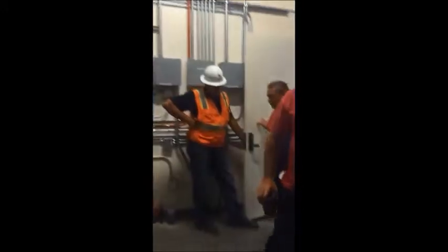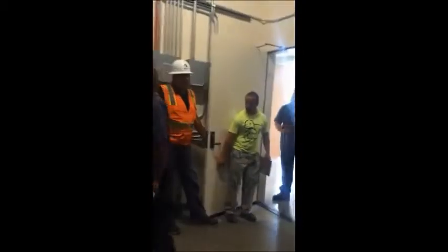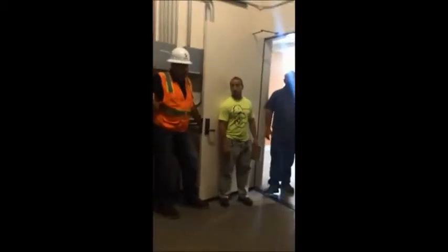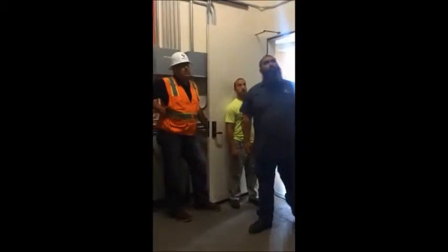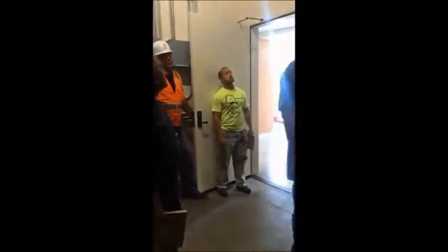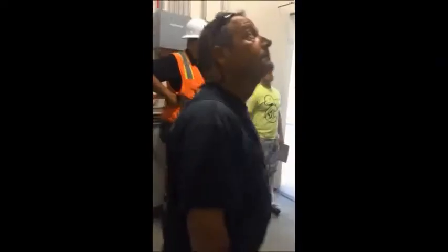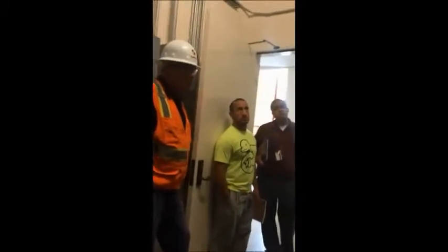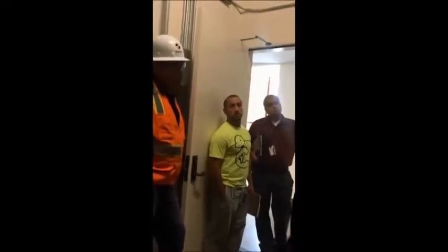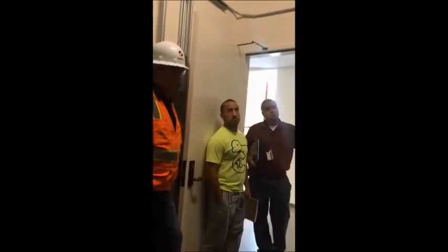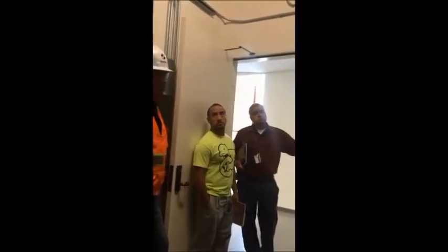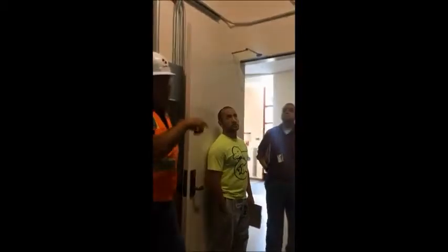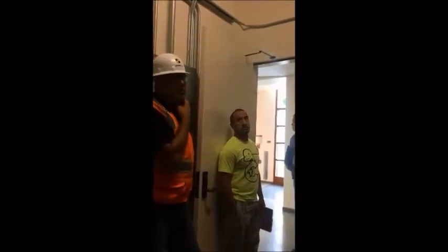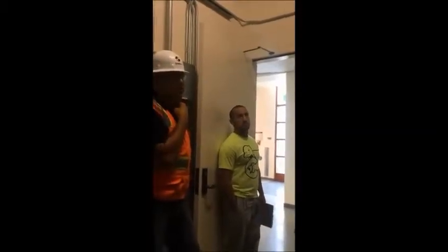Electrical room, it's the same location on level 2. It also has a fan coil unit. This is 8-1. The one above it obviously is 8-2. And then we have one exterior room, which is the one that has the 3 evaporators. So these are stacked, and there's one that's outside. And I'll show you where it's at. This one has the 3 evaps on one condenser.